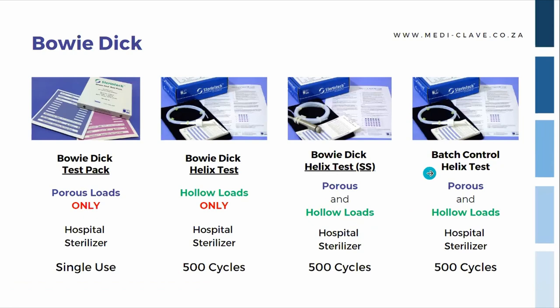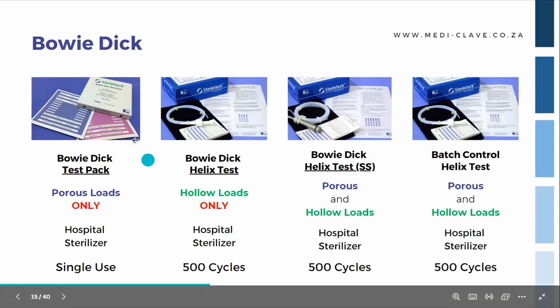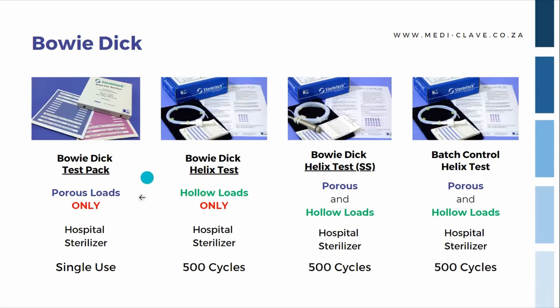And then your batch control helix test is also tested for porous loads and hollow loads, used in your hospital sterilizers for 500 cycles. Just to give you a definition of porous loads, it is minute spaces or holes through which air may pass. So a sponge is a good way to look at a porous item. Then hollow loads is having a hollow or empty space inside. So CSSD should select the correct Bowie Dick test pack based on the type of load. So for a porous load, you'll use your Bowie Dick test pack, and for hollow loads, you'll use your Bowie Dick helix test.